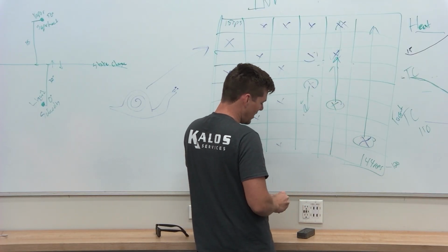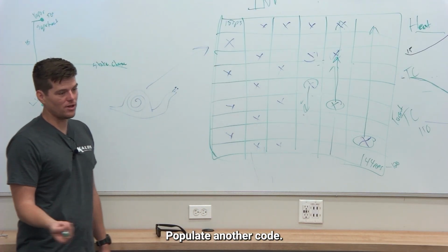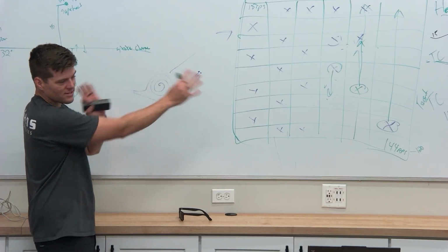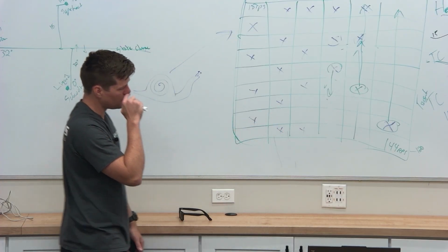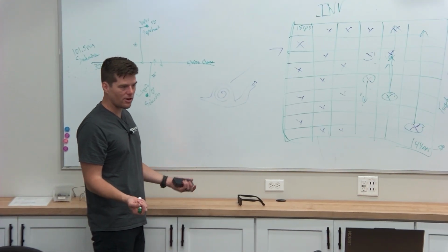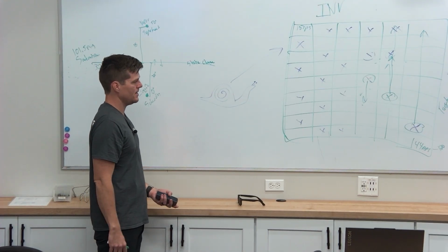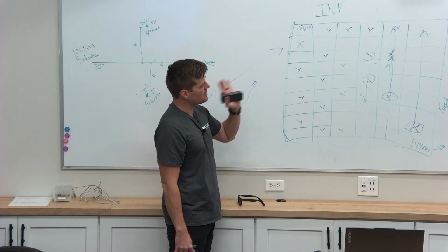And if it does that 3 times in an hour and it can't correct it, you get an F4 or an F3. You get a high discharge temp error on the system. These are all the things that it's doing all the time. So when we're looking at service checker data and we see some really crazy stuff, what do your safety controls look like? Are they dancing on and off? Are they turning on and off? Are my temperatures crazy high?